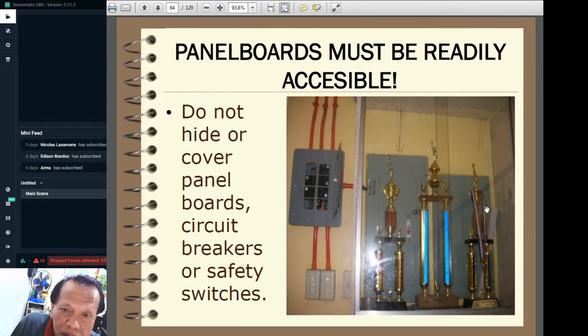And okay, here the lesson is we should not use the front of our electrical protective devices, our electrical panel boards, as display of our trophies or whatever. No, the code says that these breakers or electrical panel boards should be readily accessible, and providing this display of trophies as well as glass covering is a violation of the code.